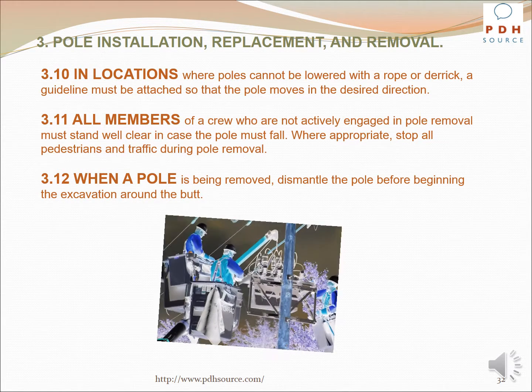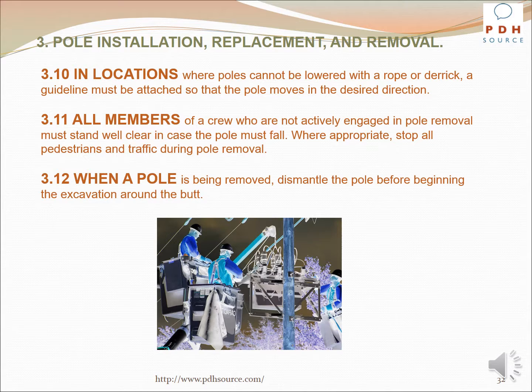In locations where poles cannot be lowered with a rope or derrick, a guide line must be attached so that the pole moves in the desired direction. All members of a crew who are not actively engaged in pole removal must stand well clear in case the pole must fall. Where appropriate, stop all pedestrians and traffic during pole removal. When a pole is being removed, dismantle the pole before beginning the excavation around the butt.